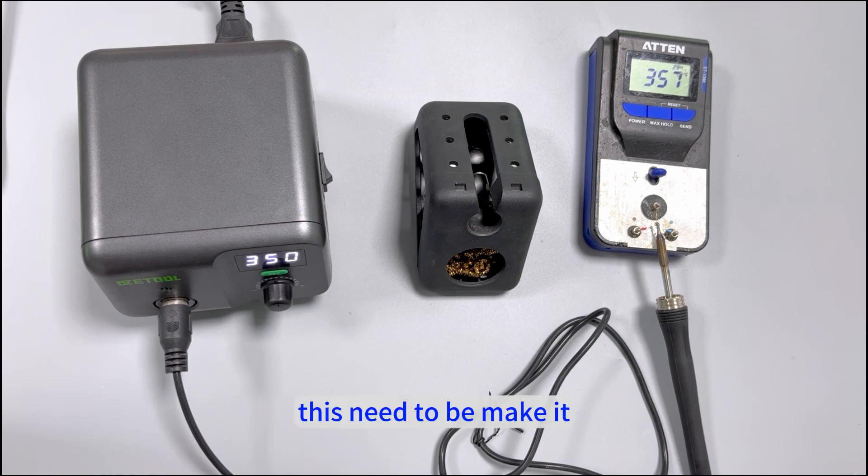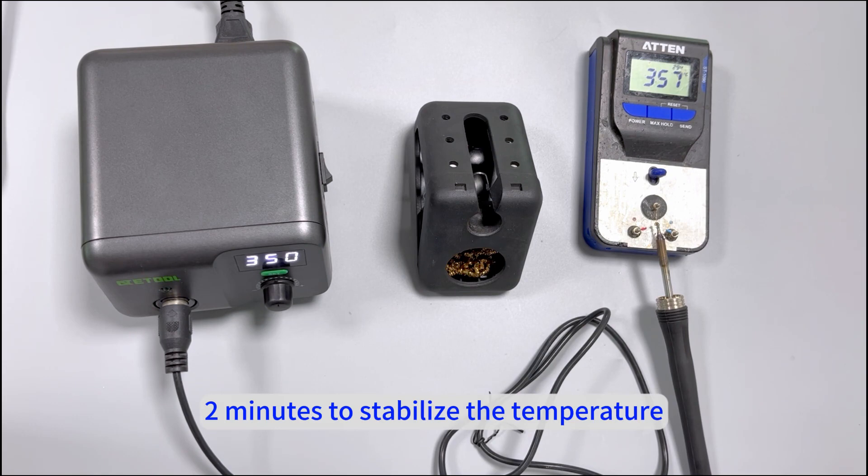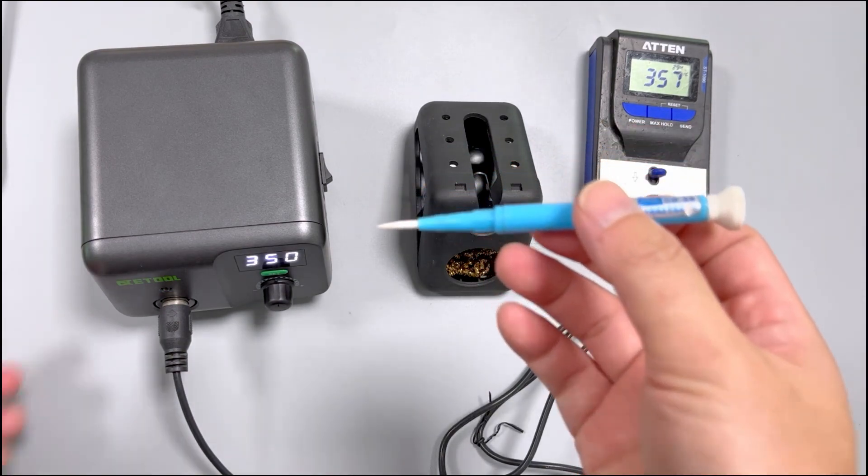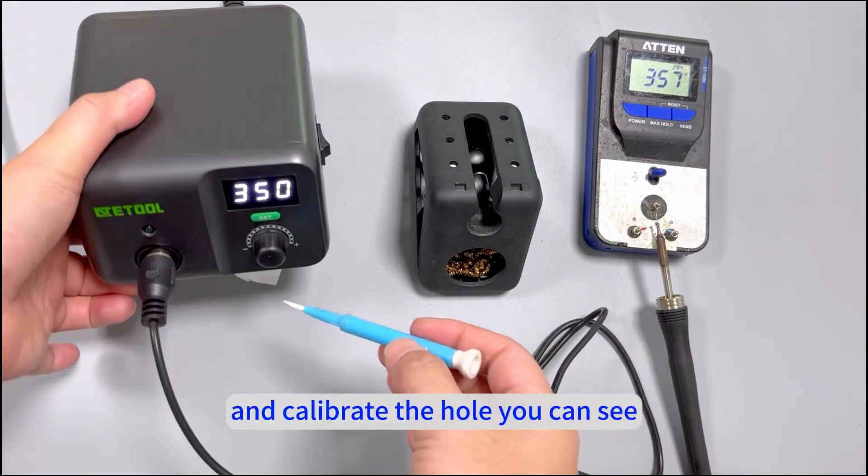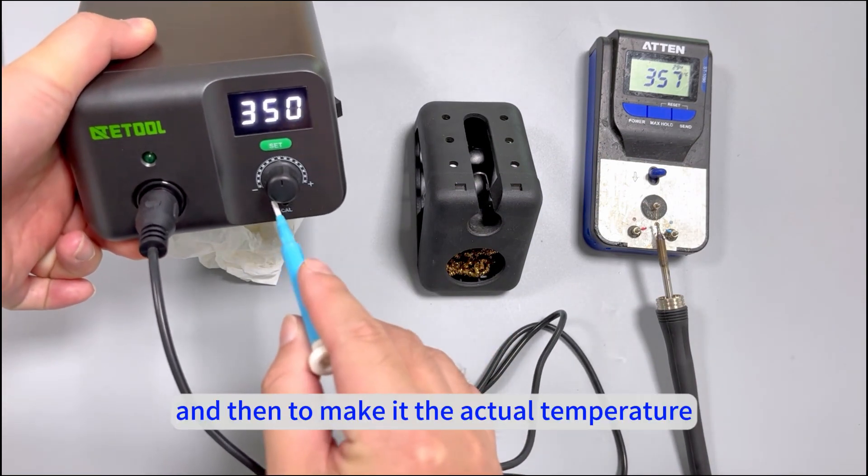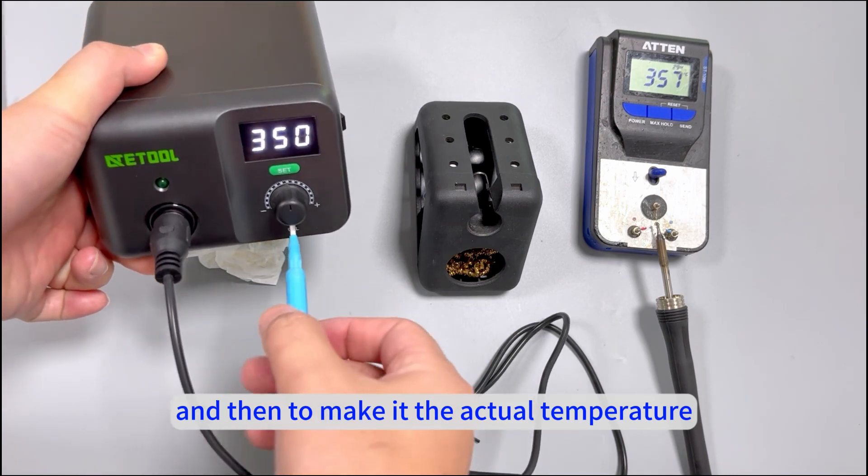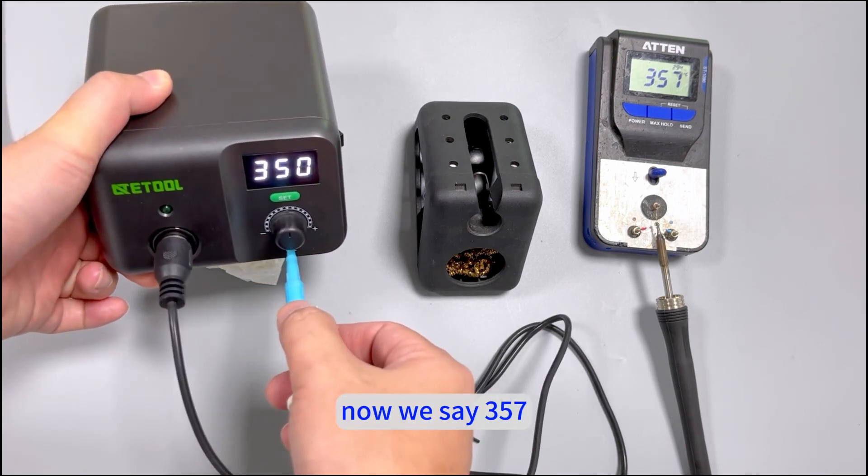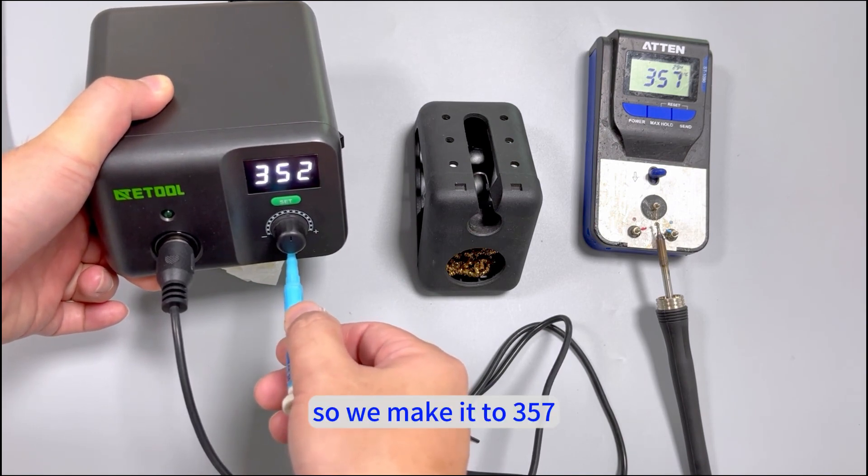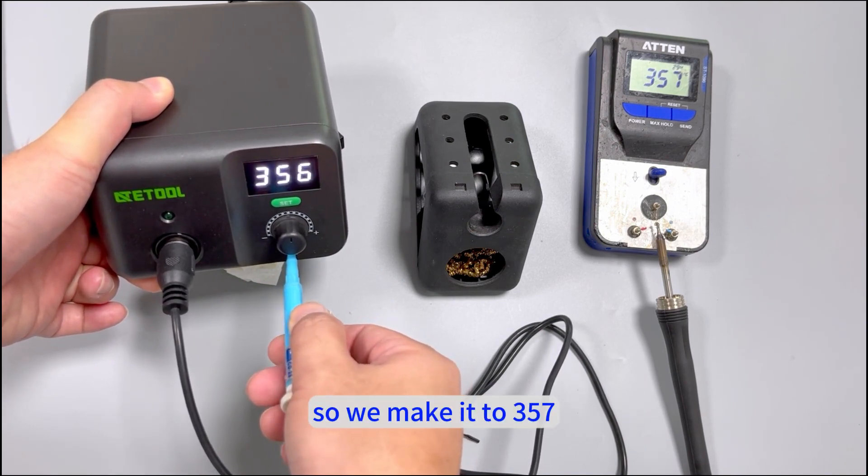We need to wait 2 minutes to stabilize the temperature. Then we use a screwdriver to calibrate the hole and make it the actual temperature. Now we see 357, so we make it 357.